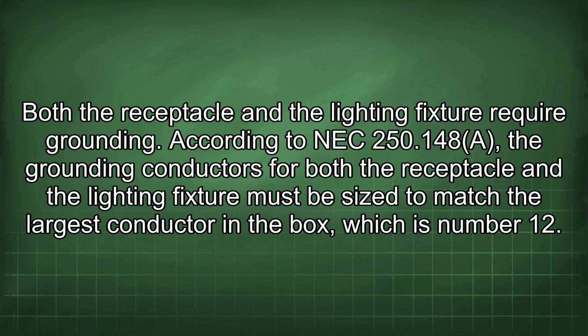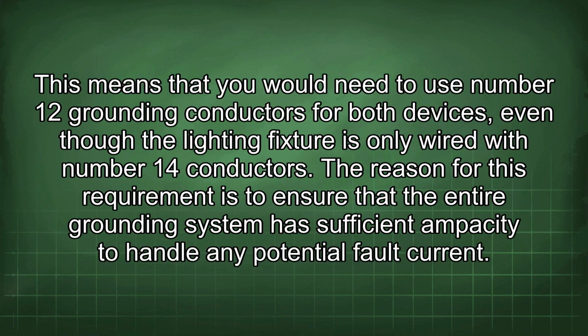According to NEC 250.148(A), the grounding conductors for both the receptacle and the lighting fixture must be sized to match the largest conductor in the box, which is number 12. This means that you would need to use number 12 grounding conductors for both devices, even though the lighting fixture is only wired with number 14 conductors.